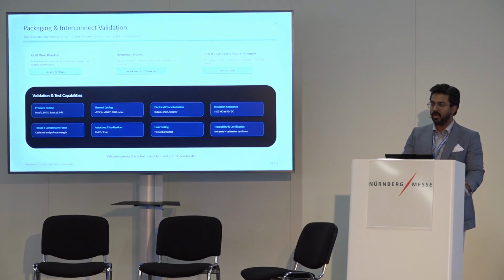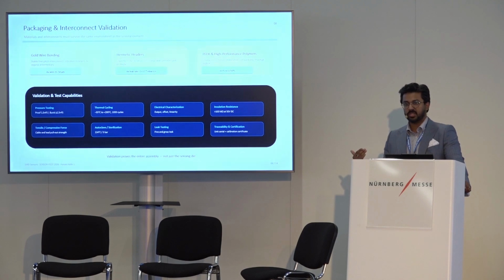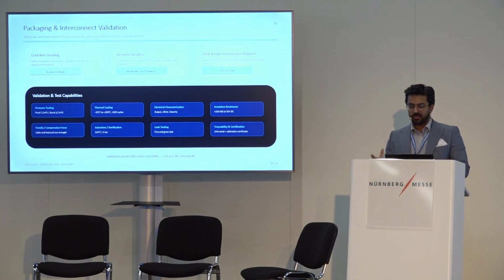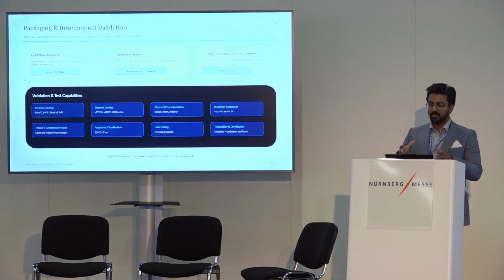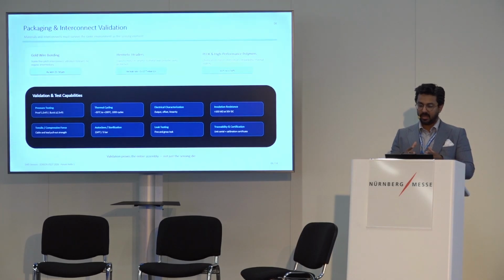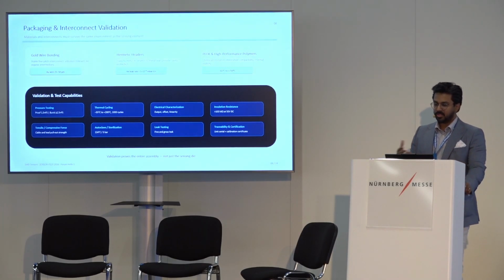Again, now this is more of a manufacturing and then inventory management, where we do full stack testing with correct serial numbers, right, for every sensor and every iteration of these sensors. And we provide the calibration certificates for it as well. So every sensor matches the correct calibration, and of course every sensor is different. So if the sensing element has to be in micron or nanoscale resolution, that can be optimized for every sensor, right? But ideally the point is we validate the assembly process and not just the development process, right? And that allows us to tackle what happens to the assembly over years of service, right?